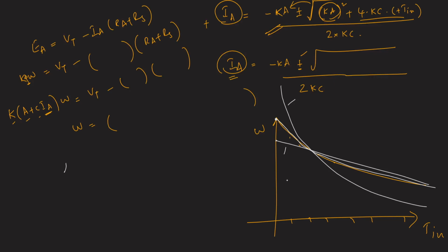Okay, now coming to the speed control, same as the shunt machine, you can find it by varying RF, the field circuit resistance, by inserting resistance in the field circuit, and by varying the applied voltage to the armature, not by varying the terminal voltage, applied to the armature through some power electronic device, and also by inserting resistance in the armature circuit, but this method is not used, like in the shunt machine.